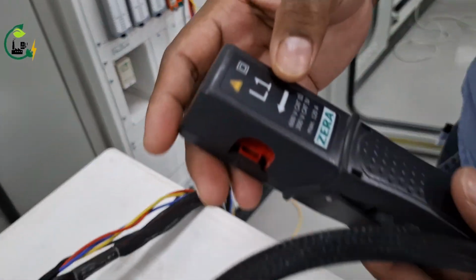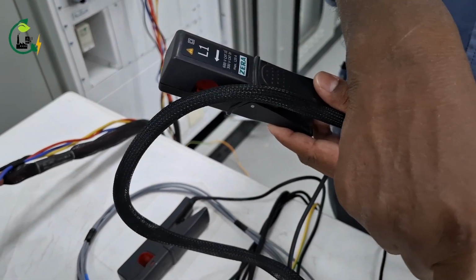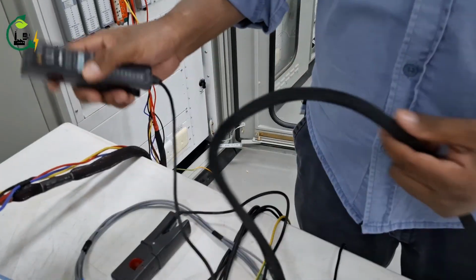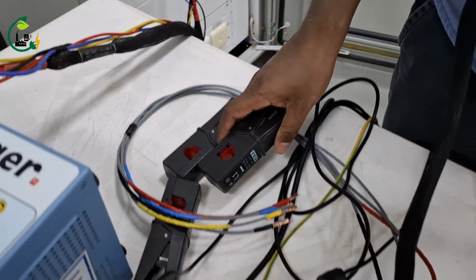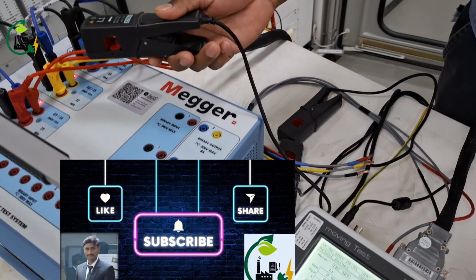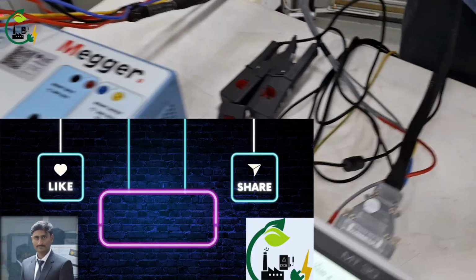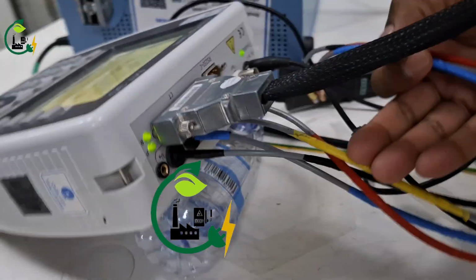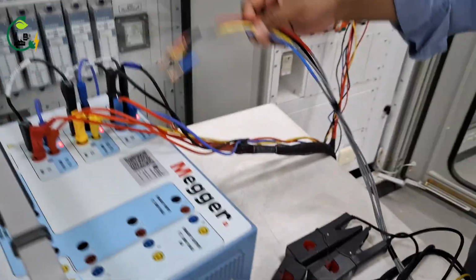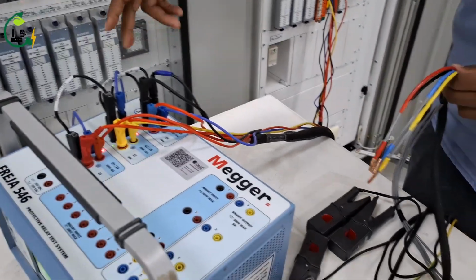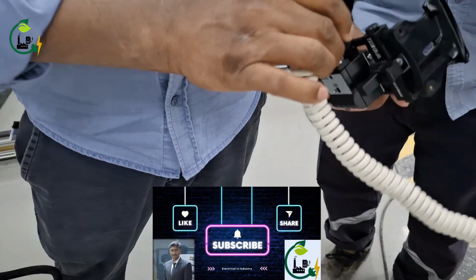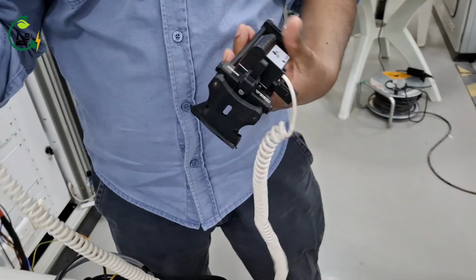For testing, for Zera, we have these 3 clamp meters. We will add them on the output current wires with the clamp. So the arrow direction should be out of the Freja, because we are applying the current from the Freja. So the arrow direction should not be towards the Freja. Connect the clamp for the CT, and for the voltage measurements, we have these 3 wires for red, yellow, blue, and neutral to the Zera kit. We will connect it in parallel to the Freja, from which we give voltage and current to the energy meter.